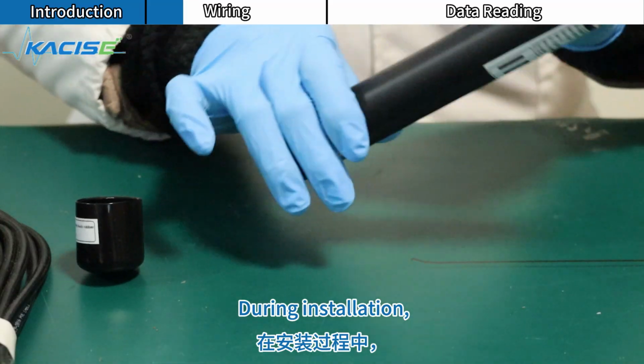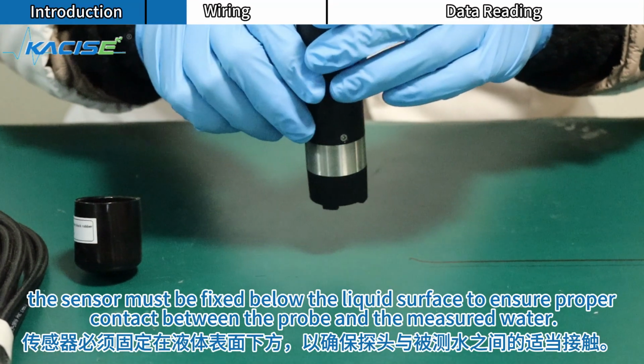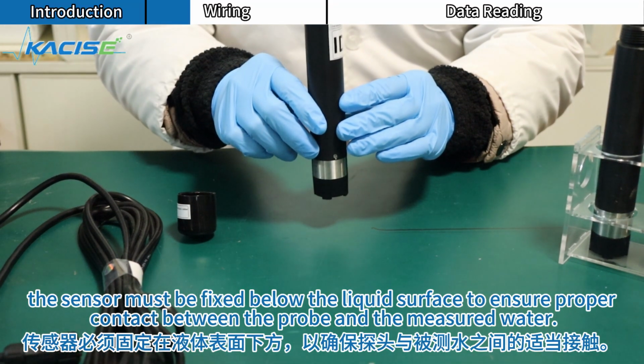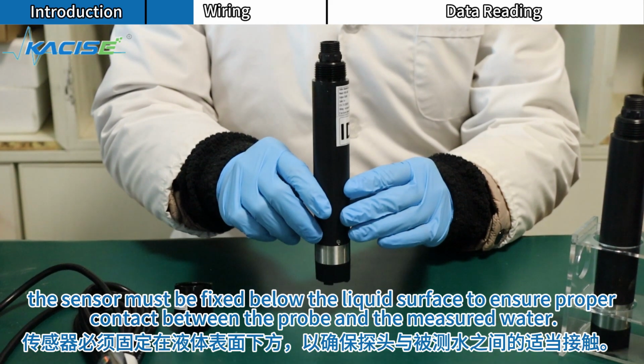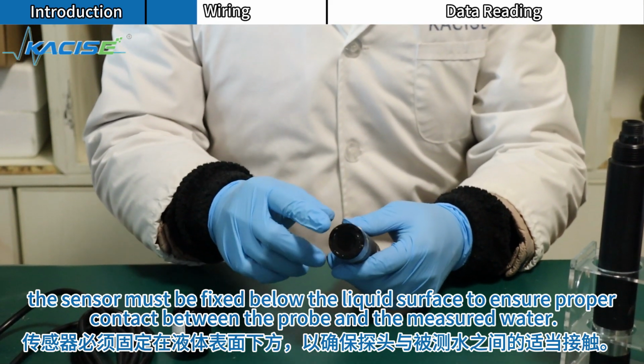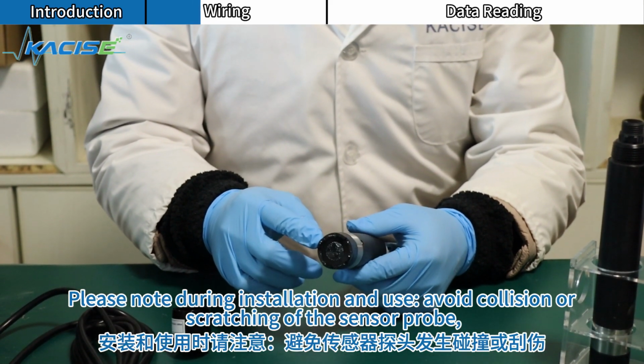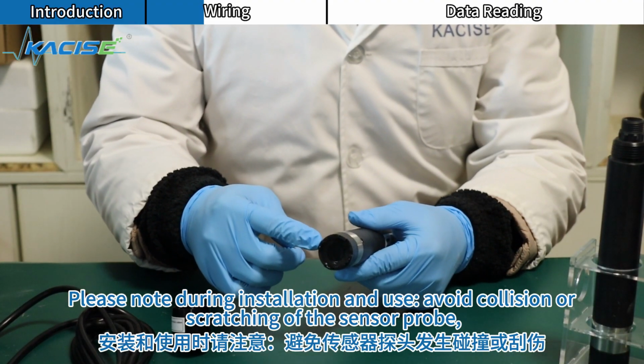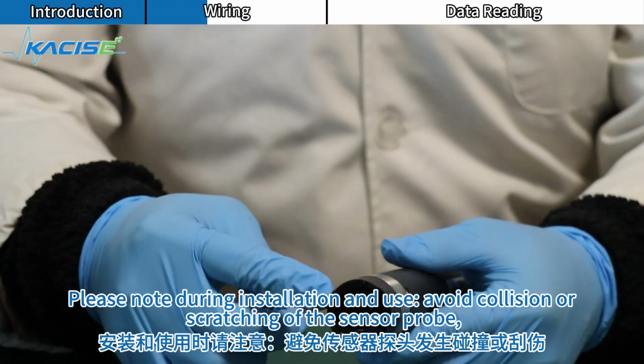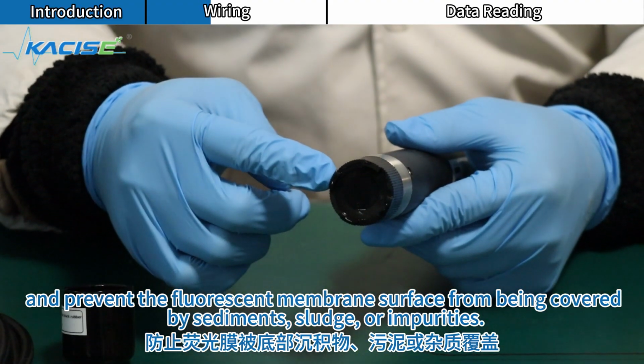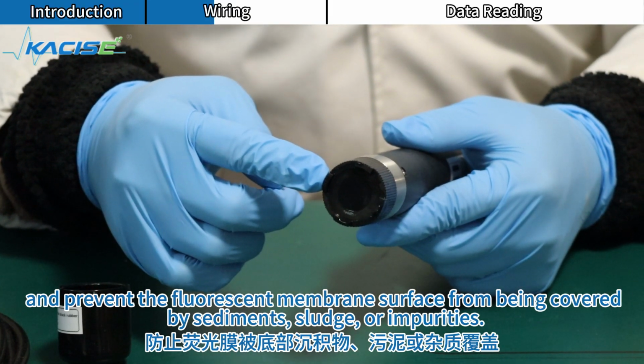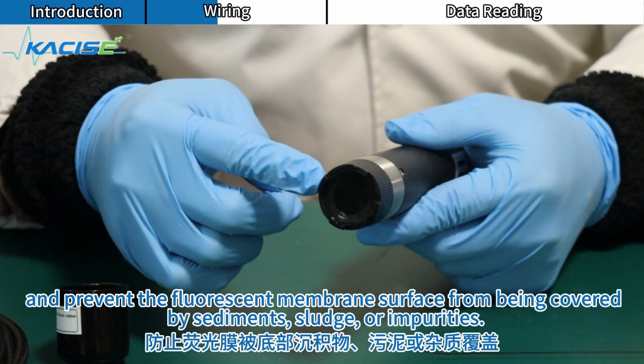During installation, the sensor must be fixed below the liquid surface to ensure proper contact between the probe and the measured water. Please note during installation and use, avoid collision or scratching of the sensor probe, and prevent the fluorescent membrane surface from being covered by sediments, sludge, or impurities.